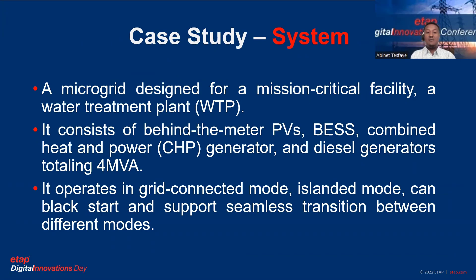The case study system is a microgrid designed for a mission-critical facility — specifically a wastewater treatment plant for one of our clients. This microgrid consists of behind-the-meter PVs, a battery energy storage system, combined heat and power (CHP), and two diesel generators, with a total microgrid capacity of 4 MW. The microgrid operates in grid-connected mode, island mode, and can perform black start and support transitions between these modes.